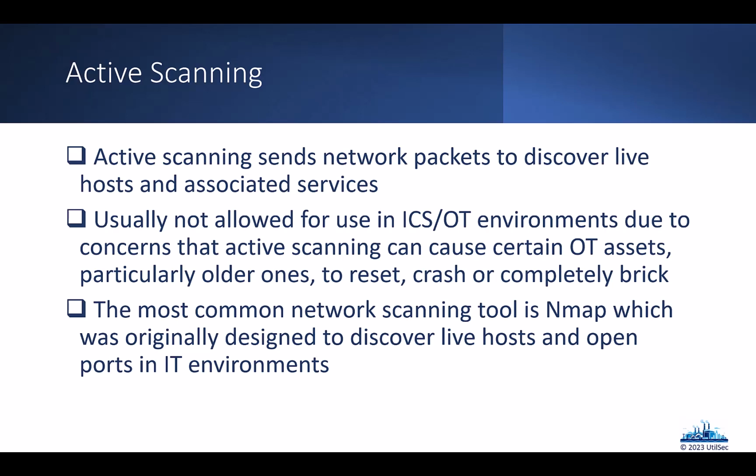The older ones don't have the troubleshooting code built into them to simply disregard a network packet they don't understand. A lot of older systems choke on packets they can't understand and have to be rebooted, or they completely die and have to be replaced, which is not what any of us want to have happen, especially in a control system environment.